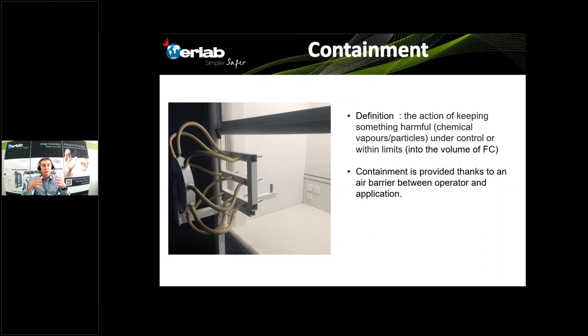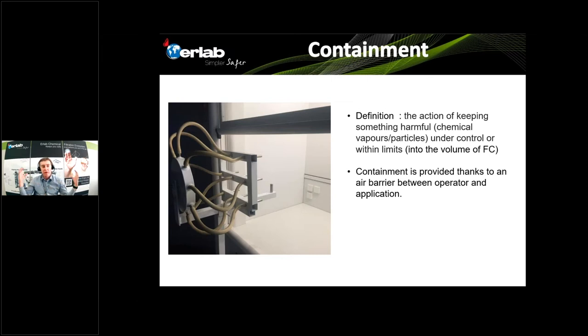When you use a ducted fume hood, all the air used to create this air barrier is extracted from the building's air volume, thanks to the fan. With a recirculatory fume cupboard, the air is not extracted from the building — it is filtered through the filters before being recycled into the room.